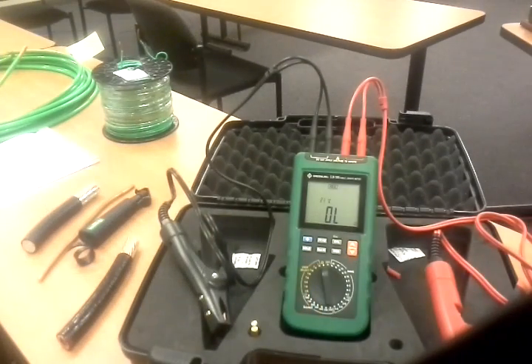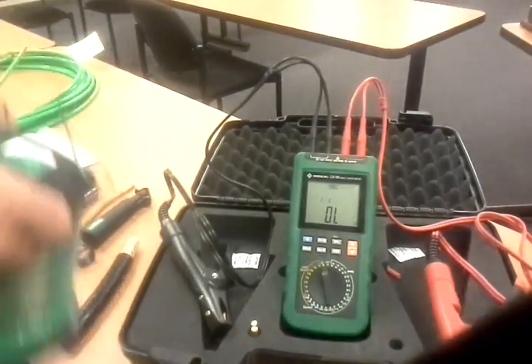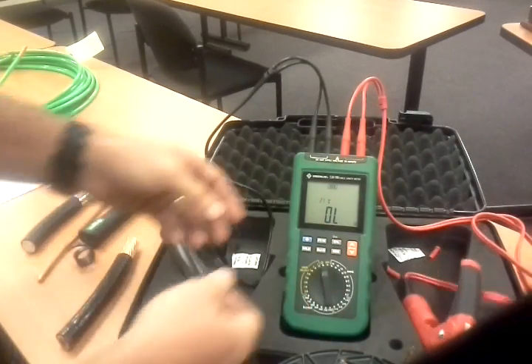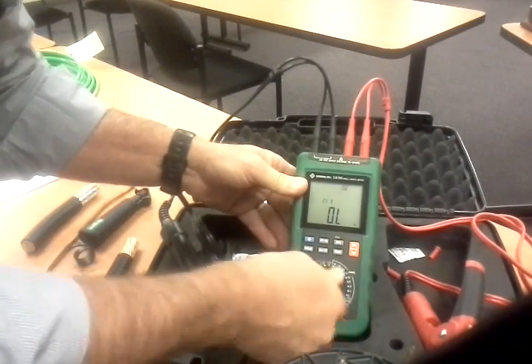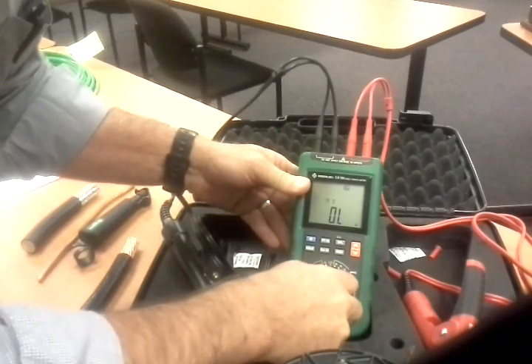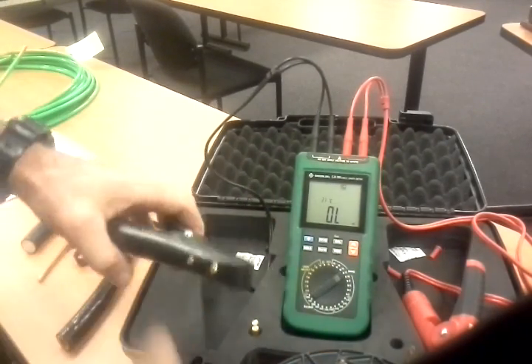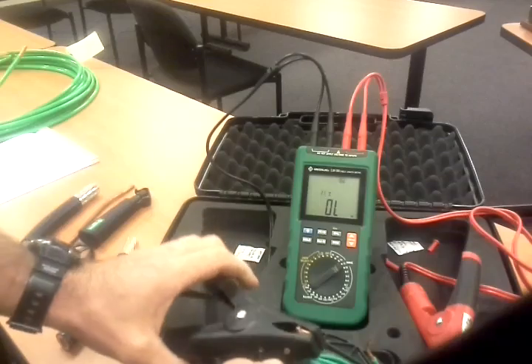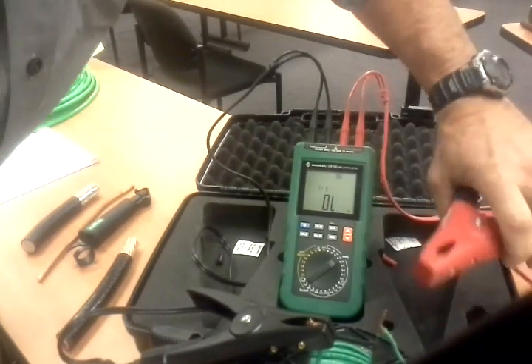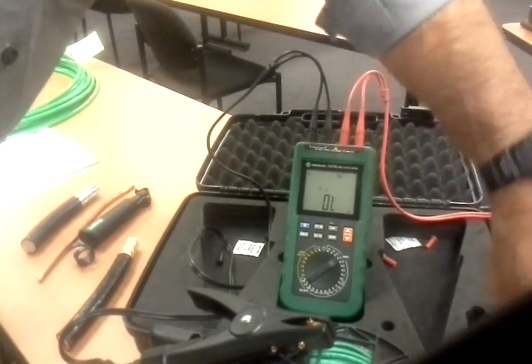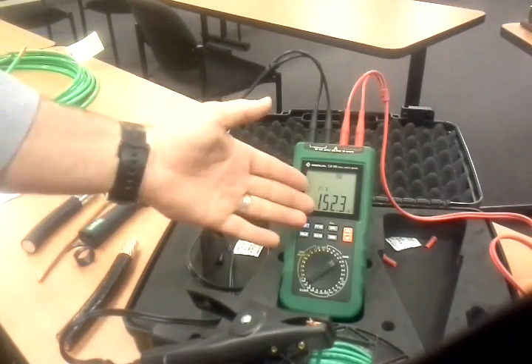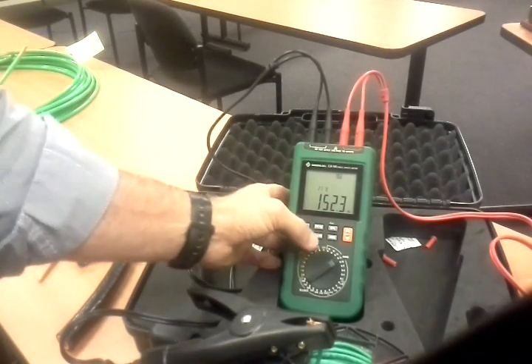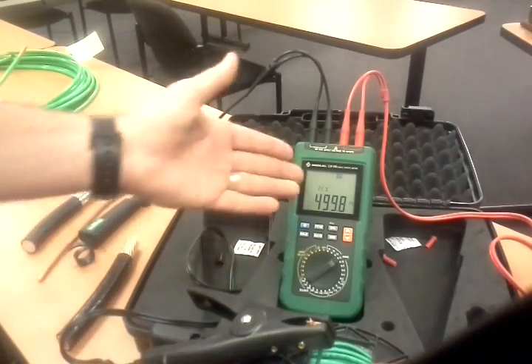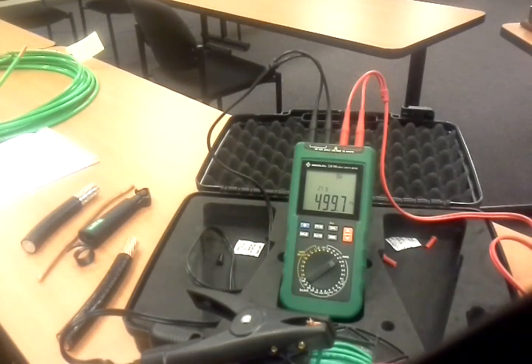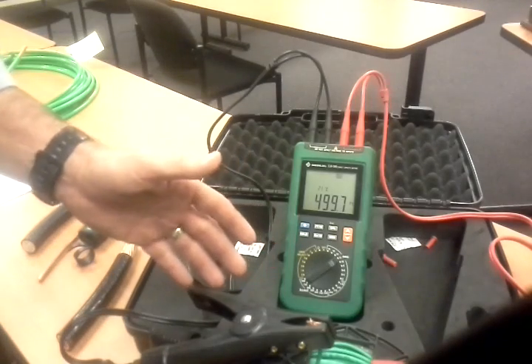Now we're ready to read cable. To demonstrate this, we'll take a 500-foot spool of 12 gauge. We'll go ahead and rotate this around to 12 gauge wire. And you simply attach the leads. This is a 500-foot spool. As you can see, we have it set up for copper, which is okay. We're going to go ahead and change it to feet and inches. The 500-foot spool is measuring 499.7 or 8 feet. And that's the way to use the Greenlee cable length meter.